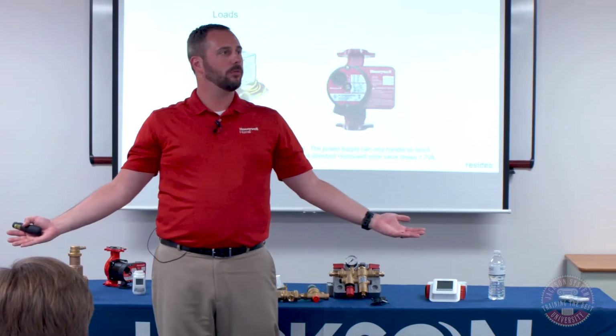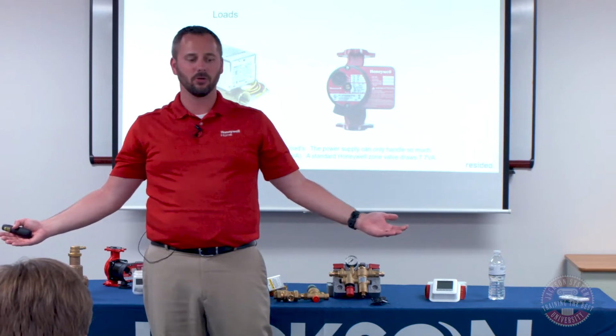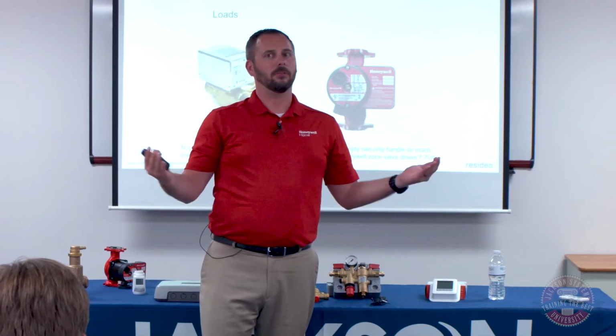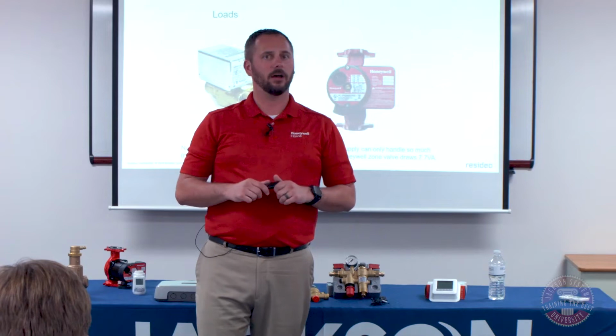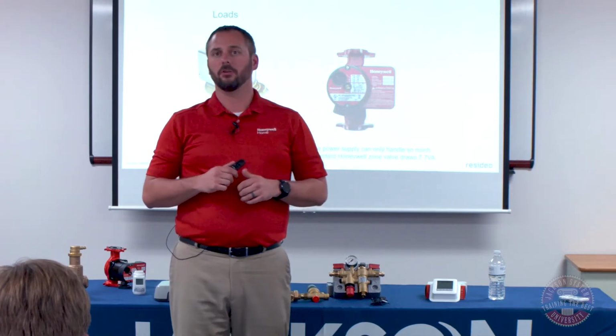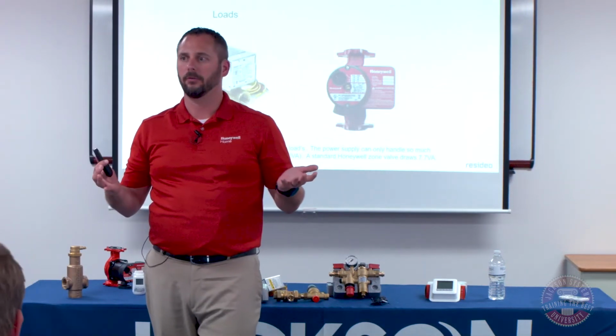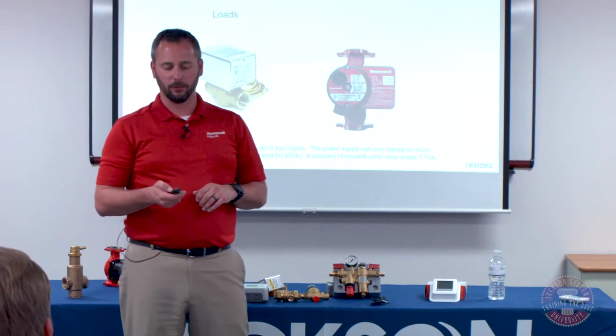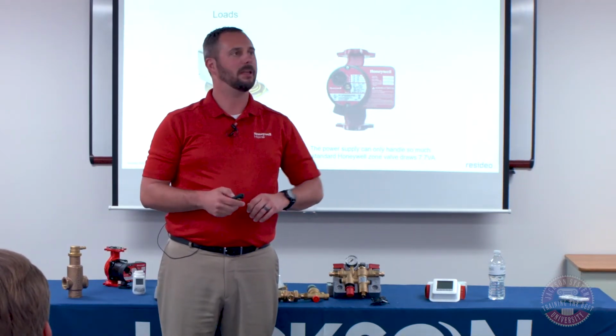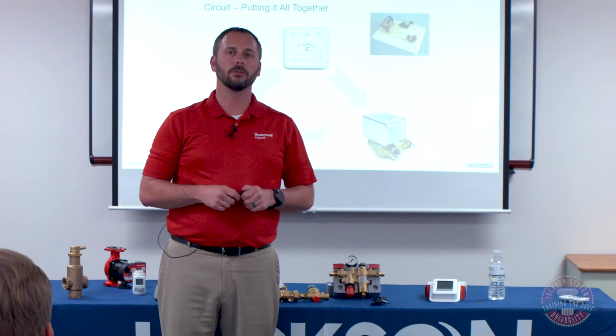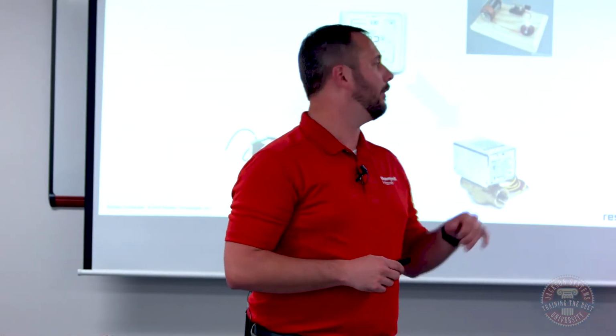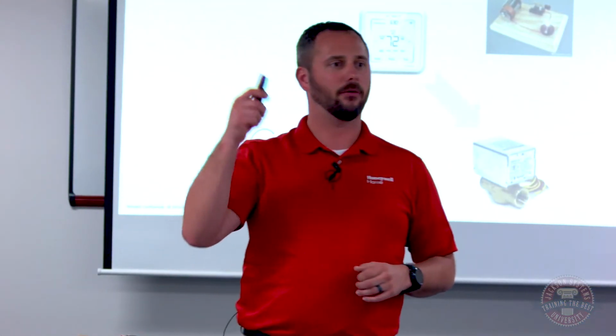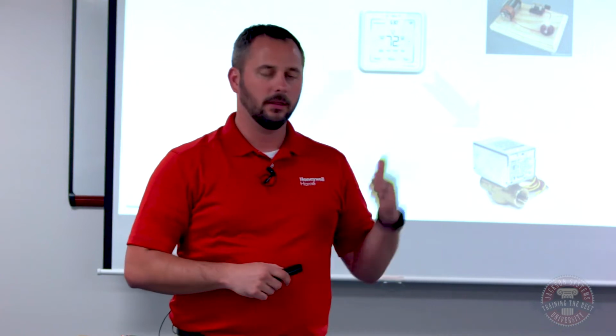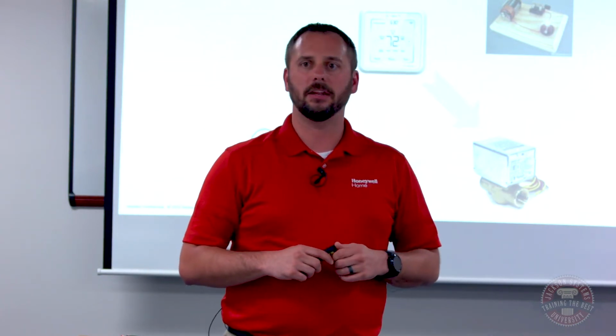And examples of load to finish up our basic, simplistic control circuit. On the 24-volt side, we have zone valves. And on the 120-volt side, we've got circulators. There can be more examples of that, but that's pretty simplistic and basic as far as what we use. When we put it all together, remember that circuit I have up at the top, battery to switch to light bulb and back? That's basically what we have in a low voltage hydronic heating circuit.